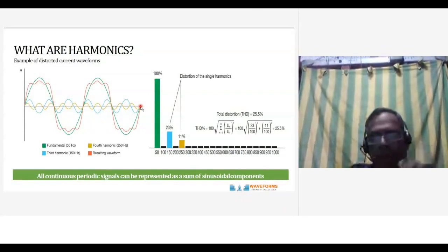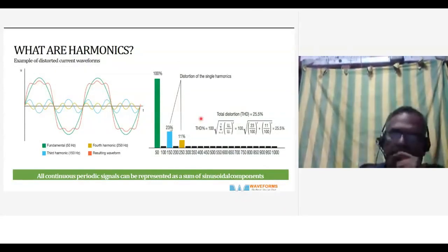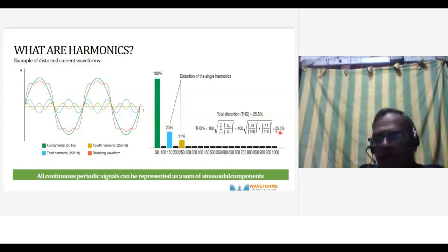So you will see this. This is a graph which shows the 150 Hz at about 23% and 250 Hz at about 11%. This is calculated in percentage: 100 into the square root of (23 squared by 100 plus 11 squared divided by 100) will give you the result. It goes on like this. If there are other harmonics, you go on adding those harmonics, and that will be the total harmonic distortion. So this is the subject that we'll be dealing with.